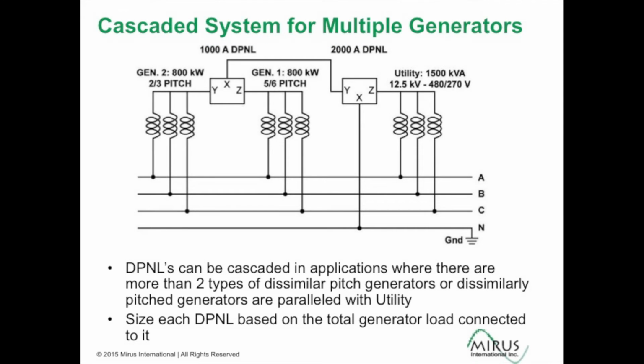Same scenario, but now the generators are of different pitches. So we have a 2/3 pitch and a 5/6 pitch. This is a scenario where we can do cascading arrangements. We can do a DPNL between the two generators to prevent the circulating current between the two generators, and then another DPNL between the combined generators and the utility transformer to prevent the circulating currents between the generators and the utility.